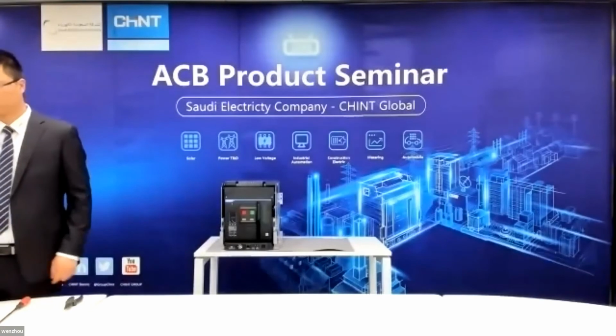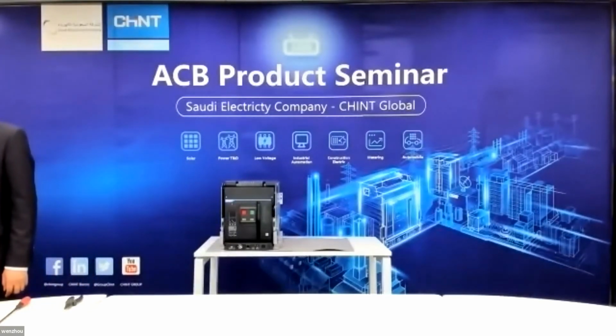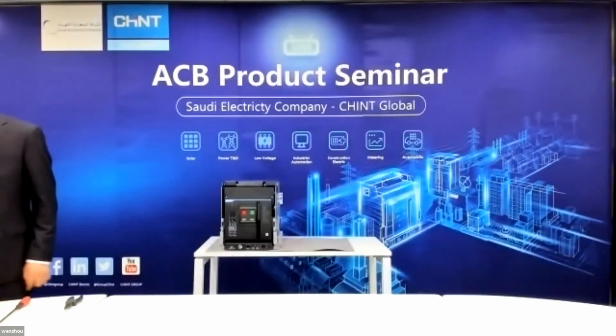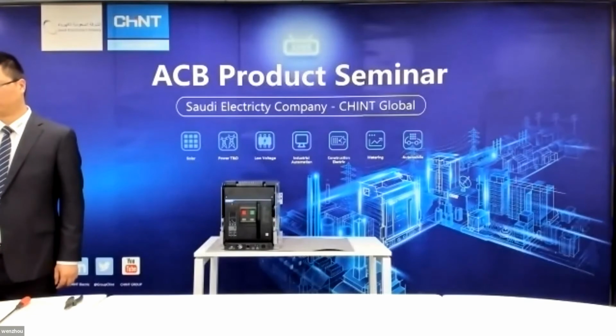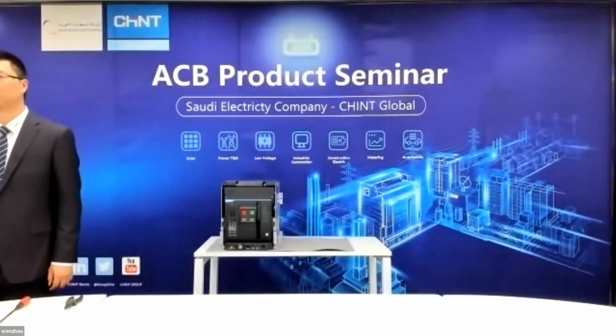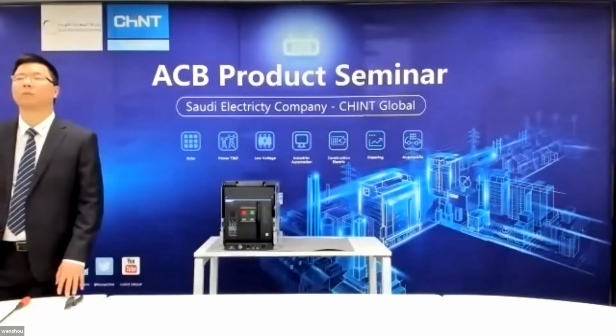Okay, welcome all. We have encountered many problems with the main circuit breaker, including earth leakage protection or ground fault, when the sensitivity is high, especially in loads including harmonics or a large percentage of harmonics like computer loads and such. What is the solution for this problem?